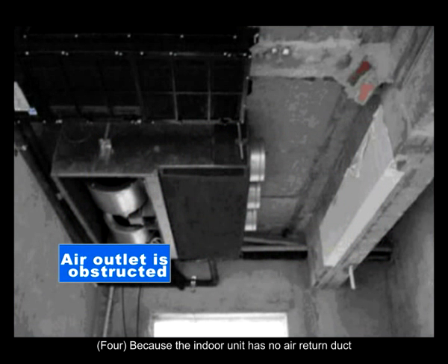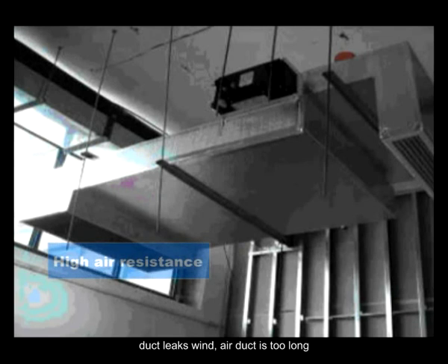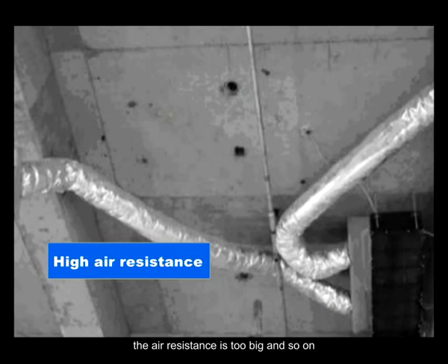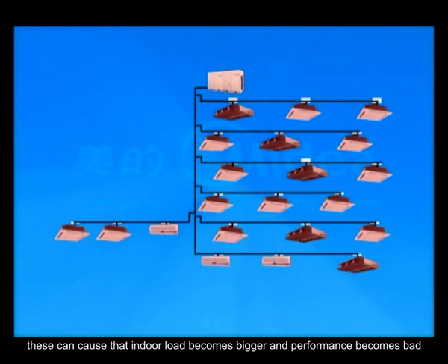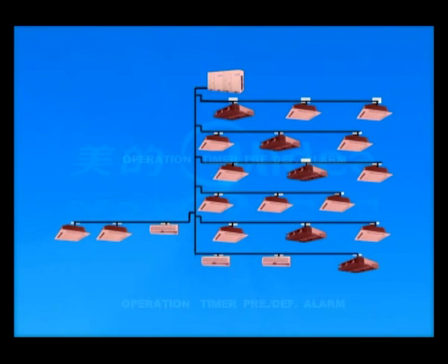4. The indoor unit has no air return duct, the duct leaks wind, the air duct is too long, or the air resistance is too big and so on. These can cause the indoor load to become bigger and performance to become bad.